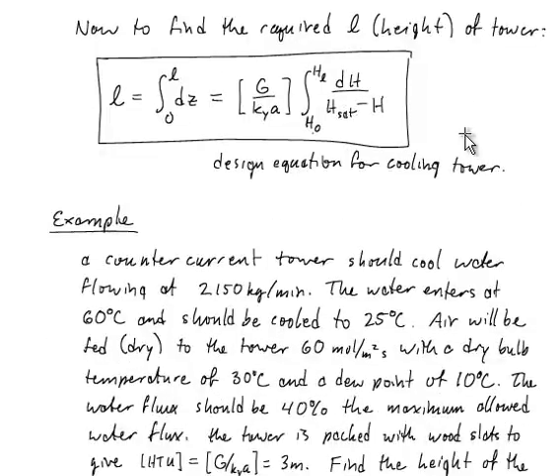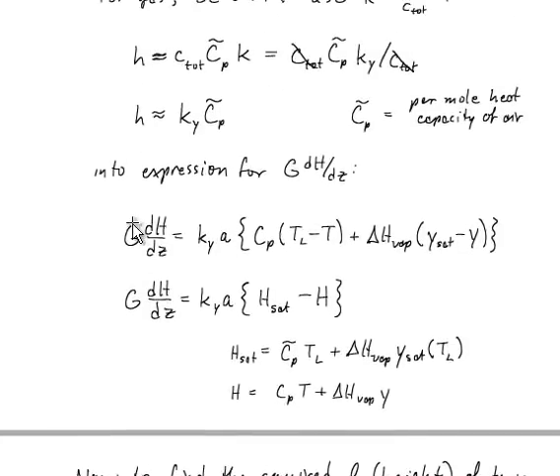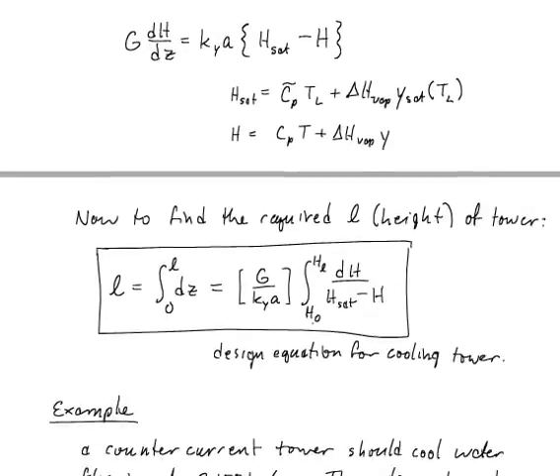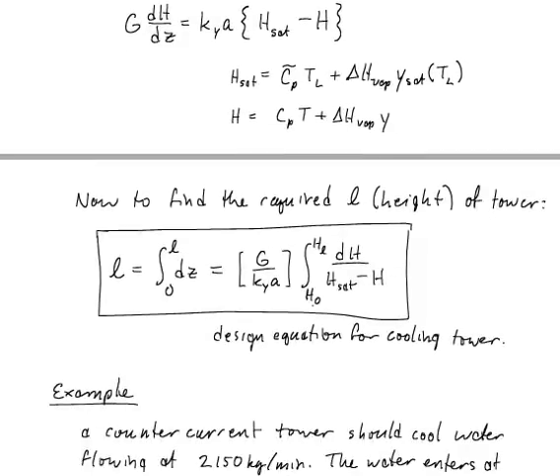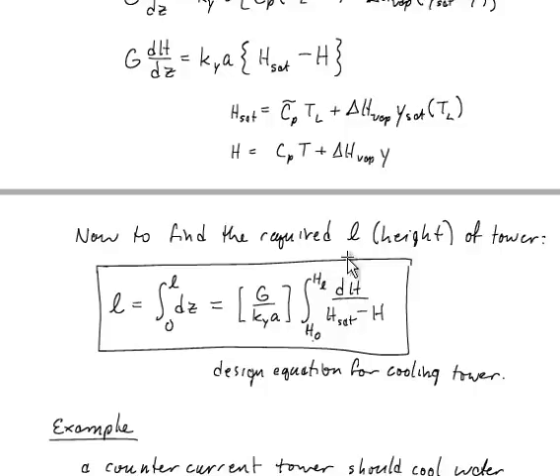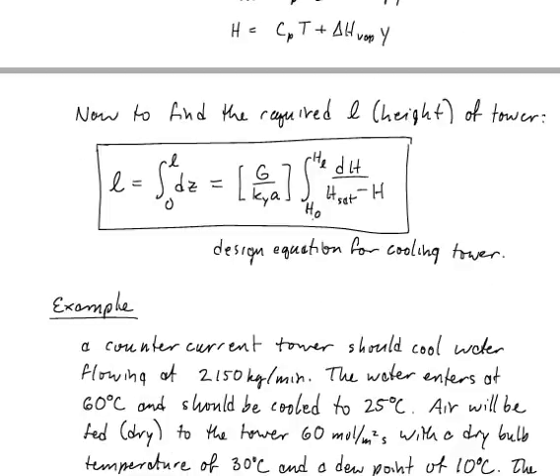The required tower height L is found by integrating the design equation. The parameter G/(Ky·A) naturally emerges and is called the Height of an Enthalpy Transfer Unit (HTU). Rearranging gives: L = (G / Ky·A) · ∫ dH / (H_sat − H), integrated from the inlet gas enthalpy at the tower bottom to the outlet enthalpy at the top. This integral must be evaluated numerically but yields a prediction for the tower height needed to cool a given water stream by a given amount.